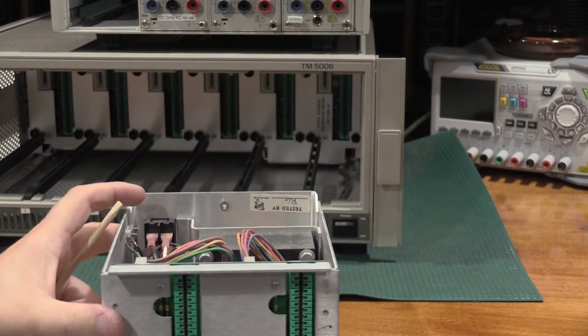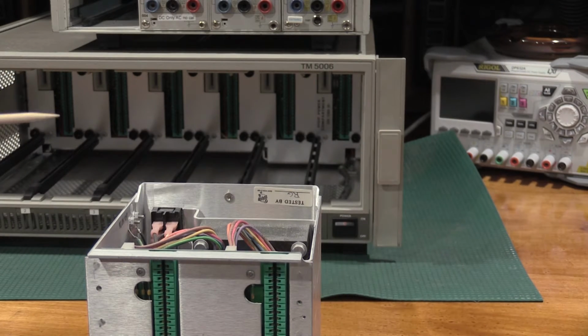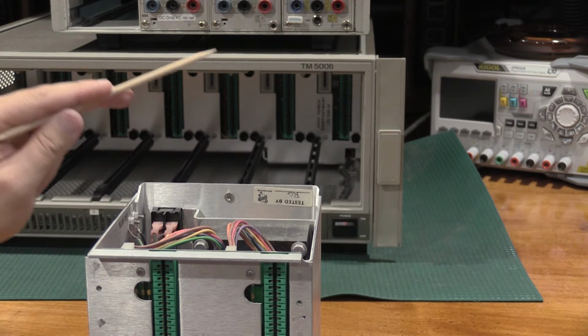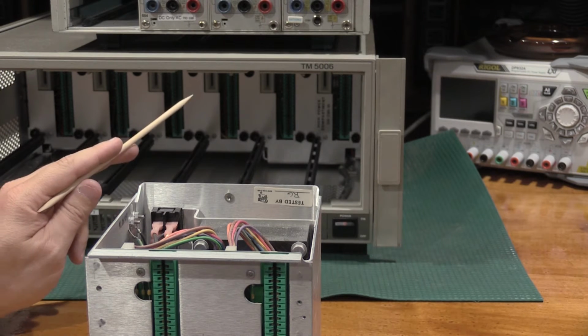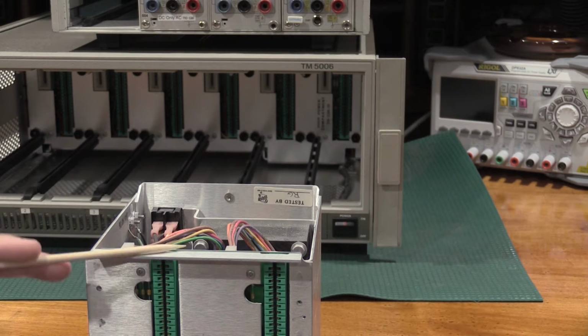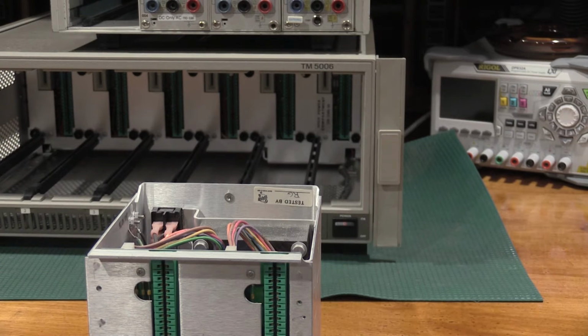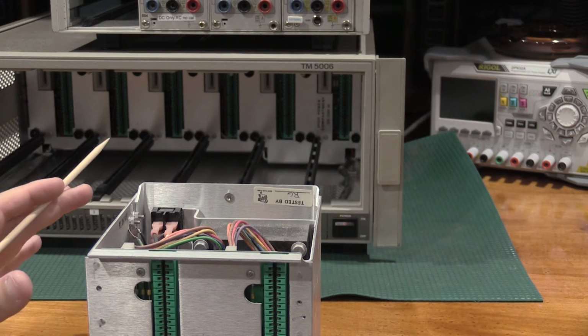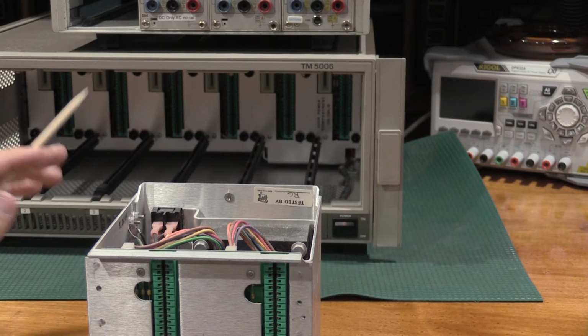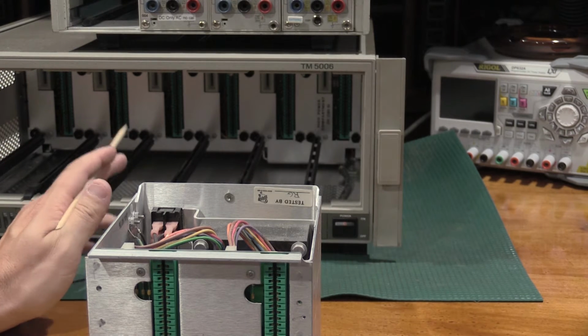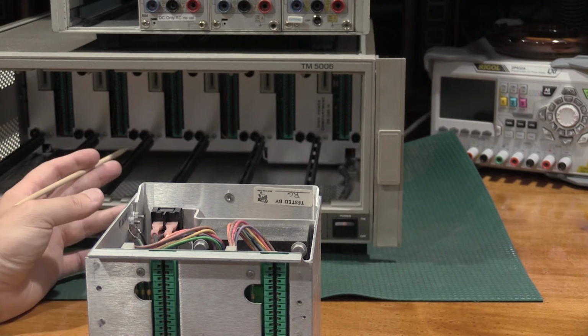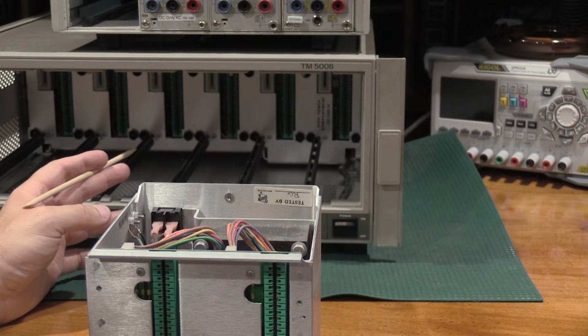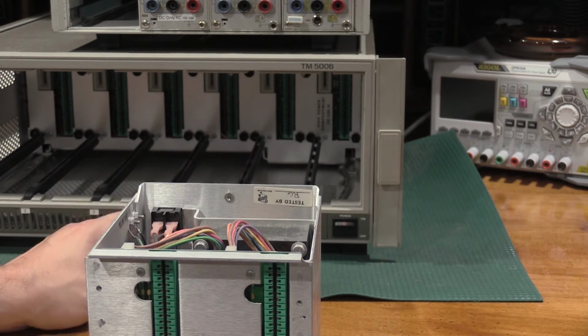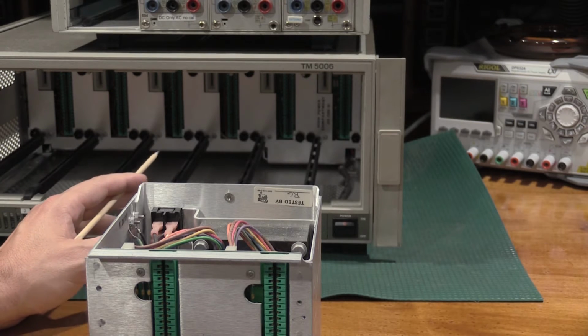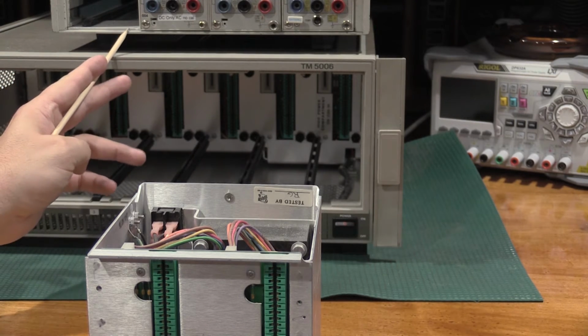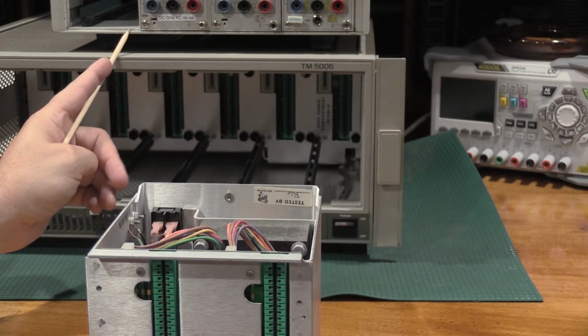That gets me into one of the main differences between the 500 series and the 5000 series. The literature might say they're incompatible with each other. The 500 plugins can go in a 5000 bay. The 5000 plugins cannot go in a 500 bay. The other main difference between the two power bays is the 5000 series tends to be actively cooled. Now the 5 and 6 bay of the 500 series, you start getting a fan. 4 bays and under in the 500 series, they're passively cooled.